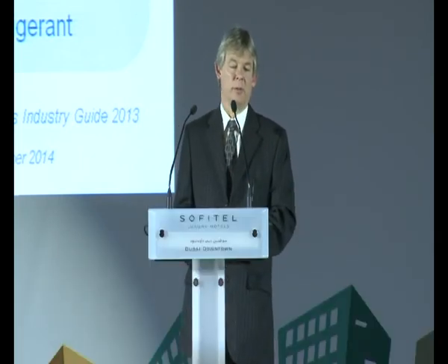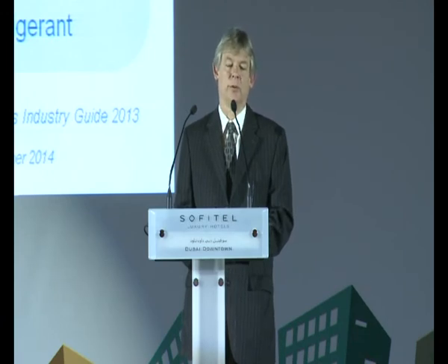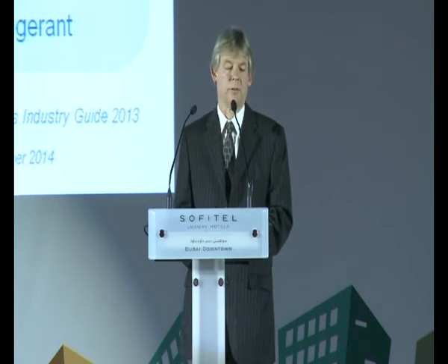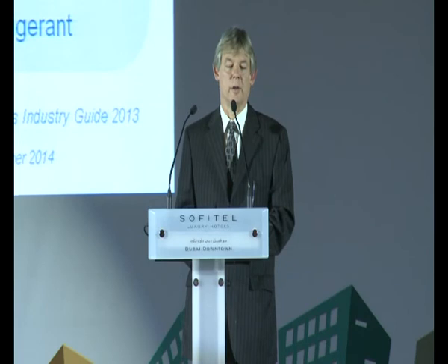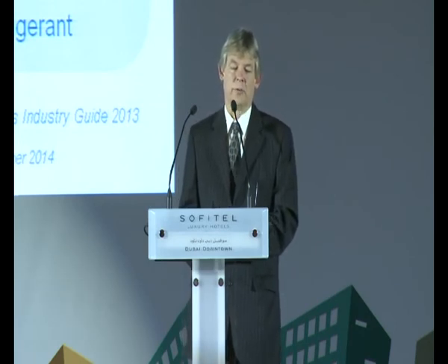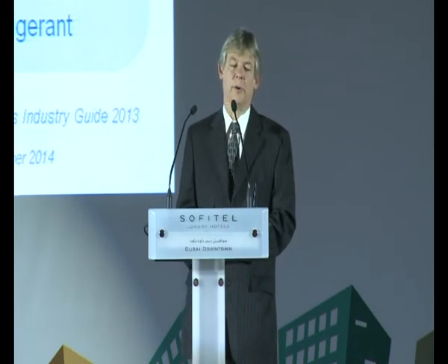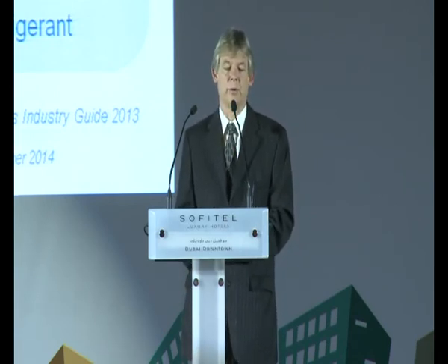Reclaiming of the charge. The machine used for refrigerant recovery must be suitable for use with flammable refrigerants with no potential sources of ignition. HFC refrigerant recovery machines may not have been approved for use with flammable refrigerants. Approval must be sought from the manufacturer before using a standard HFC recovery machine with any flammable refrigerant. Some machines may be safe for use with flammable HFCs, but not hydrocarbon refrigerants.